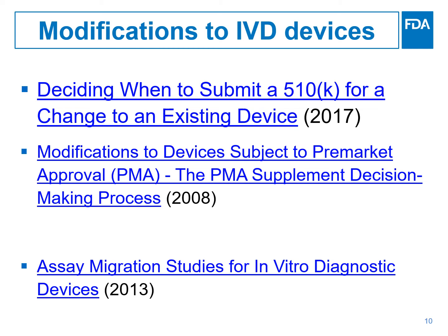In the next slides, I will focus on the first one, deciding when to submit a 510(k) for a change to an existing device. This is because most of the IVD devices are Class 2, but I wanted to make you aware that Class 3 devices have different requirements, and as such, we have a separate guidance listed here under bullet number 2. I also wanted to make you aware of the assay migration guidance, which is specific to devices that are subject to PMA and also for certain assays that require a 510(k).